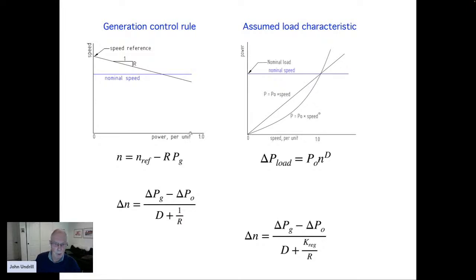The generators prefer to operate at fixed power in many cases because their machinery is thermal. Temperature range in a gas turbine is 1500 degrees centigrade, and change in temperature causes expansion and contraction and internal stresses in the machinery. And the operators don't want to do that. So there are good reasons why many power plants don't operate under drooping control. And this K_reg is not one. We'd like it to be one, but it's frequently 0.3.